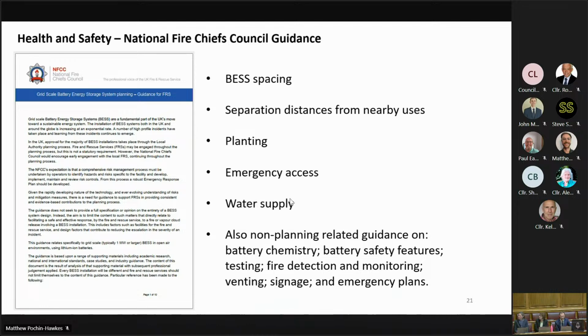BESS facilities should be separated by an initial minimum of 25 metres from surrounding uses and buildings. There should be no combustible planting within 10 metres of a site. For emergency access, there should be 2 accesses to account for wind speed and direction. For water supply, there's a minimum recommendation for hydrants delivering no less than 1,900 litres per minute for 2 hours, which equates to 2,280,000 litres of water.